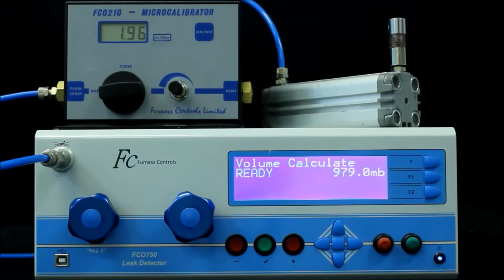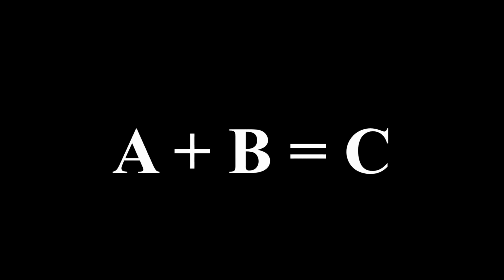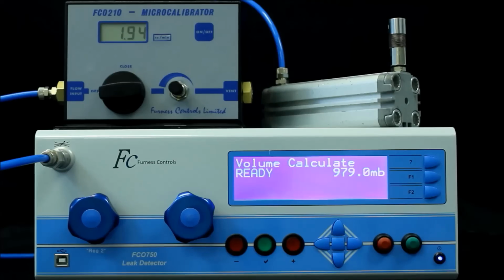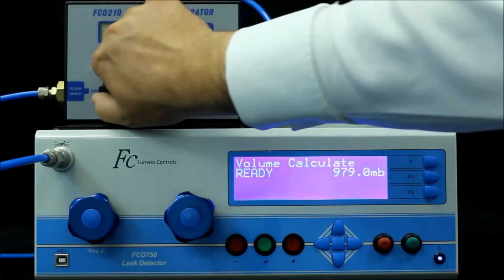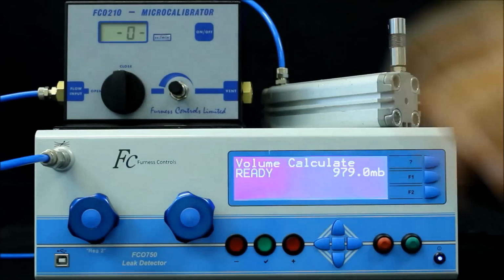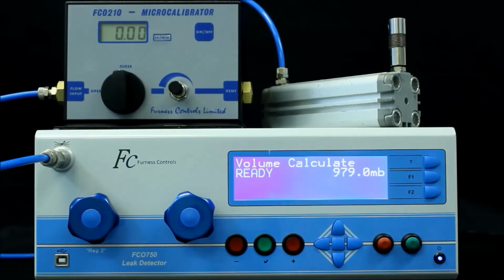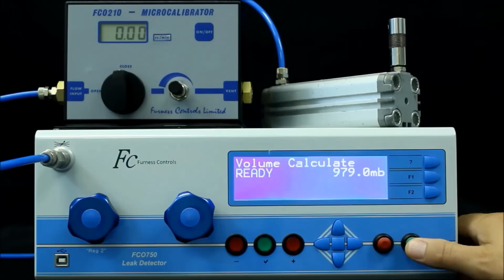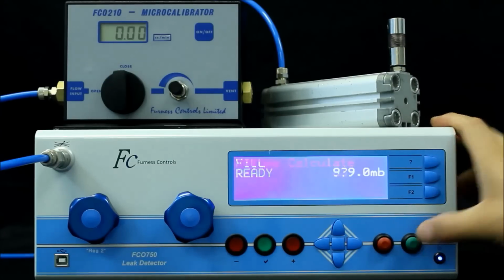Right, so the principle of this test is going to be A plus B equals C. And I'll explain that right now. I'm going to close the valve on the micro calibrator so there's no leak induced, and I'm going to run a test with my non-leaking part.